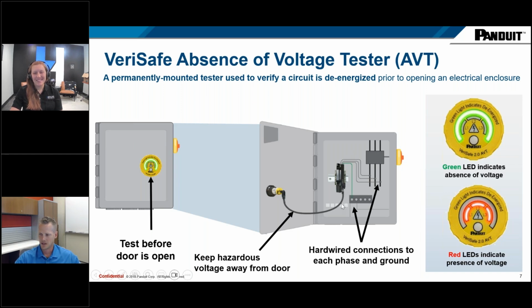From there, there's the system cable, which is just an Ethernet cable that is connecting out to your HMI that's on the panel door, right? So when you've got that panel door shut, what you see here is this device, and you initiate by pushing the button, and it sends a signal and kicks off the series of questions and tests that it's running on the system that it's permanently installed to. Common illuminations you'll see on the face of the indicator are red LEDs if everything's humming away and everything's energized. And then once you get an absence of voltage confirmation, you'll get a green illumination here indicating that it is safe to enter.